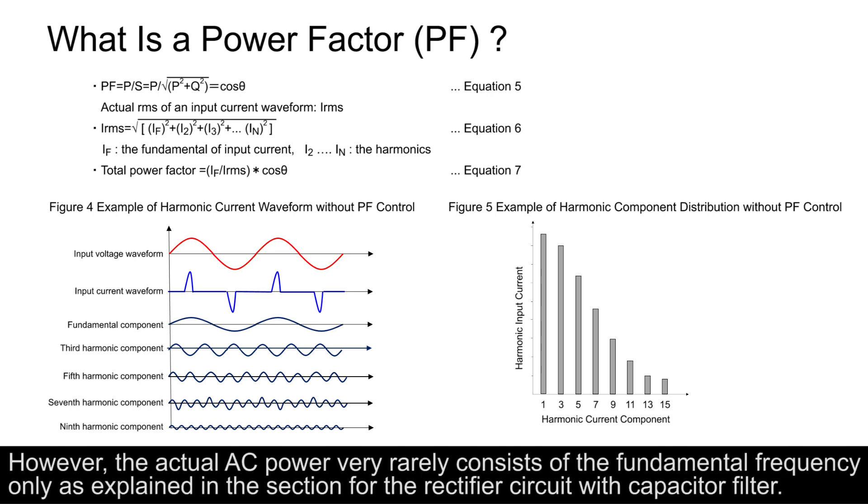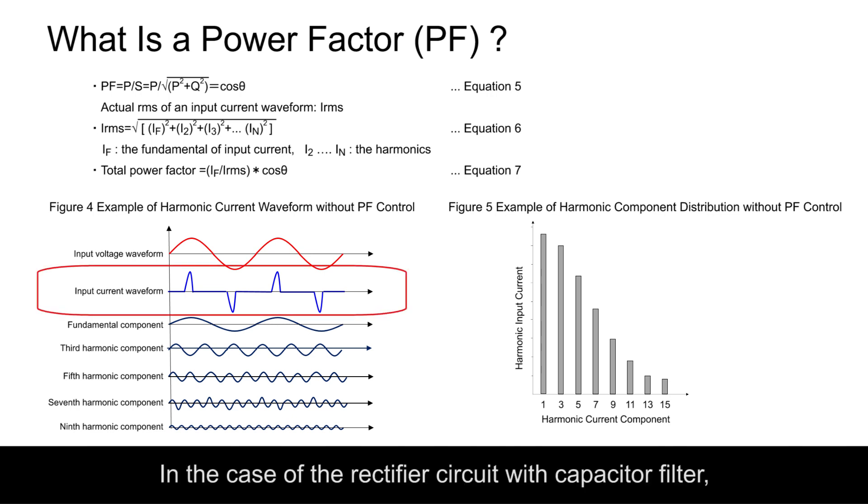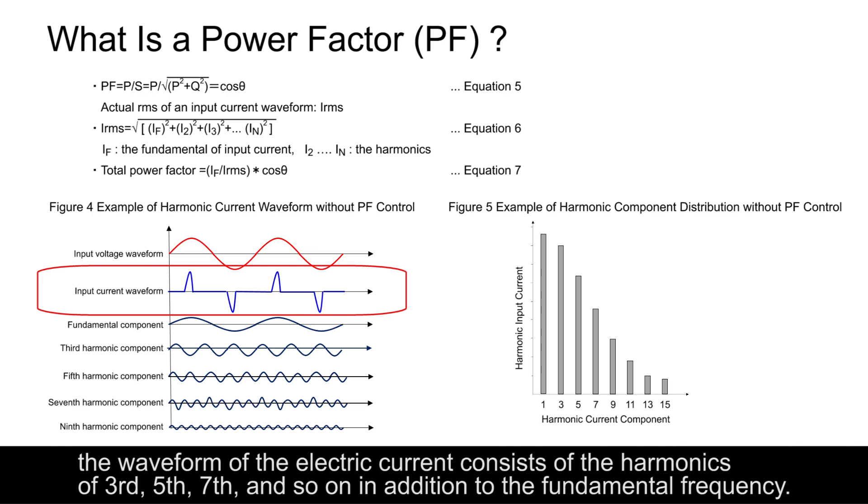However, the actual AC power very rarely consists of the fundamental frequency only as explained in the section for the rectifier circuit with capacitor filter. Figure 4 shows the waveform in this circuit. In the case of the rectifier circuit with capacitor filter, the waveform of the electric current consists of the harmonics of 3rd, 5th, 7th, and so on, in addition to the fundamental frequency.